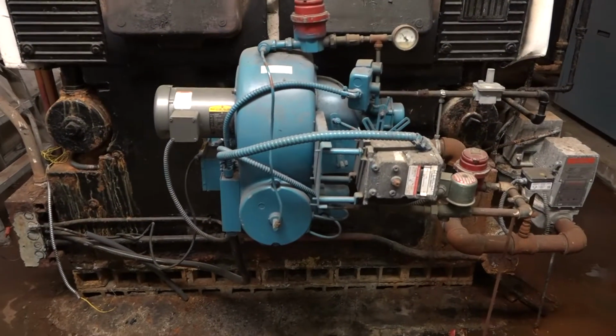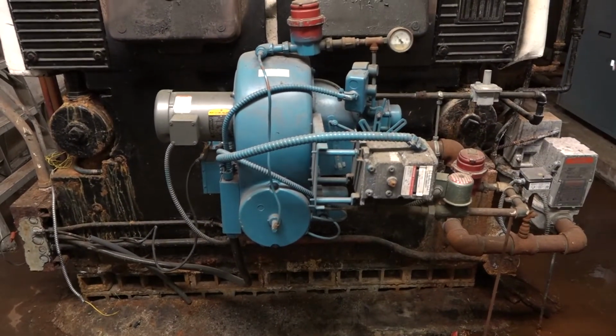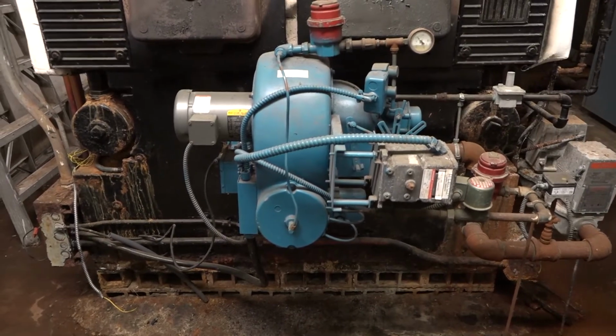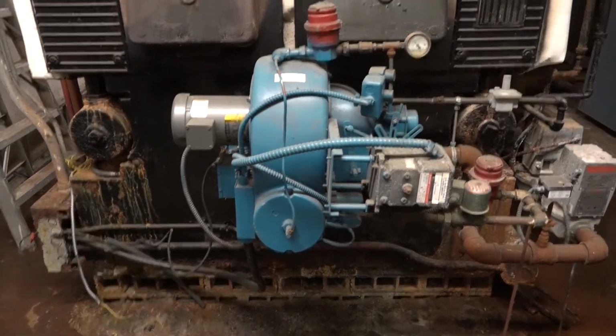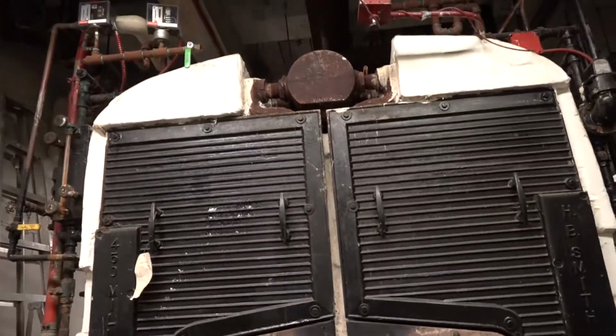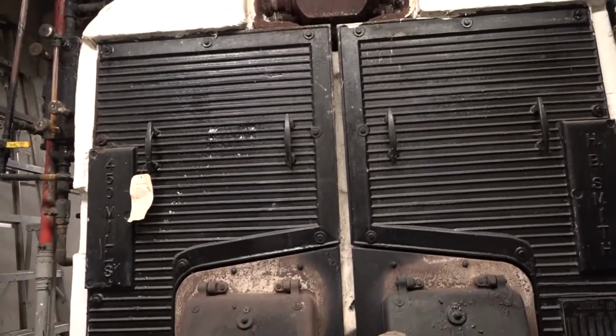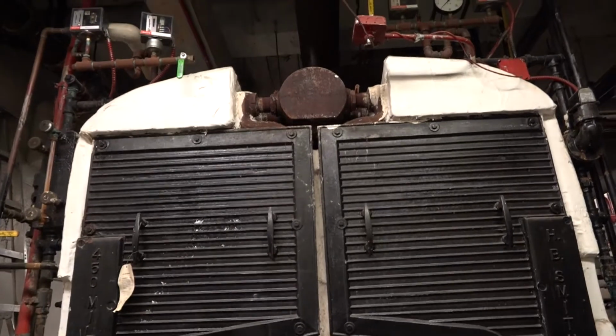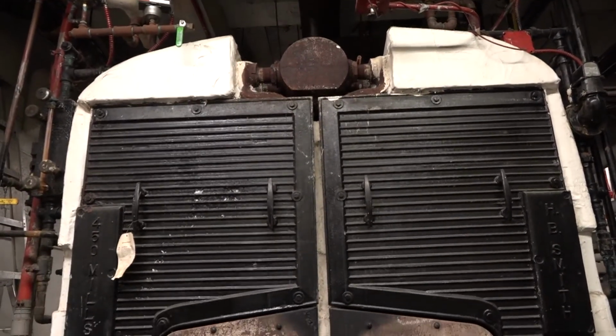This is where the condensate from the boiler actually drains down into this drum in all the sections. There's 13 sections in this boiler. So each section has a drain, so the condensate comes down into the mud drum, goes back to the condensate return tank, and then gets pumped back into the boiler.